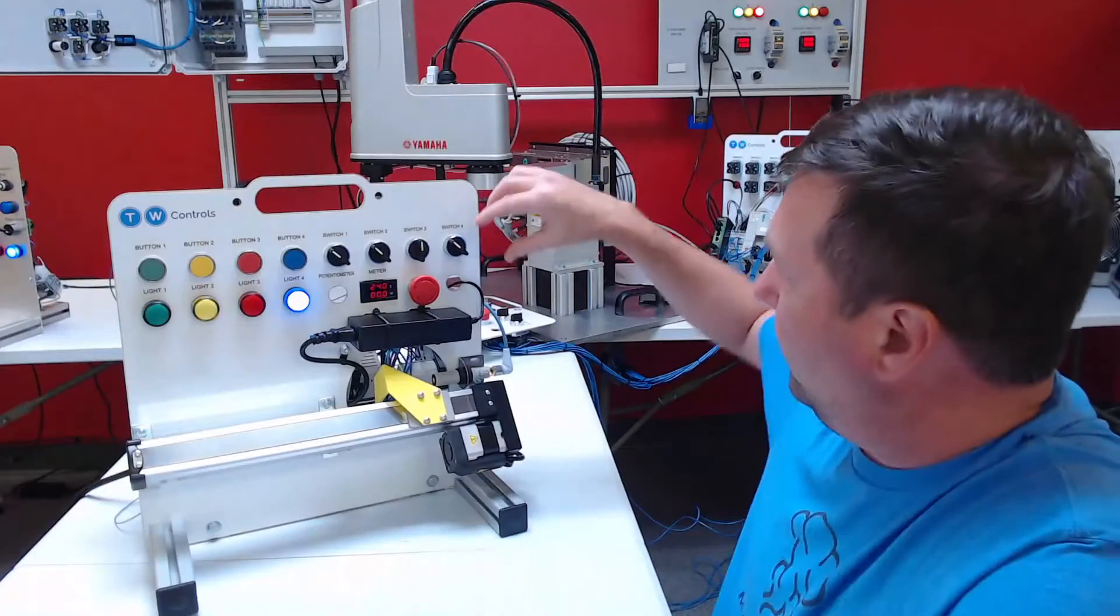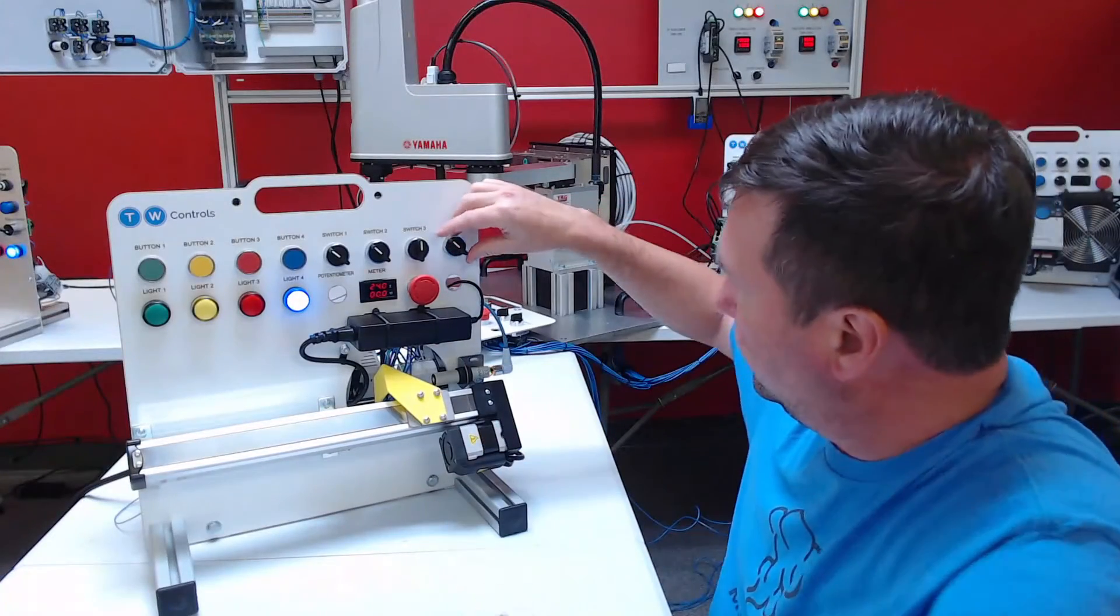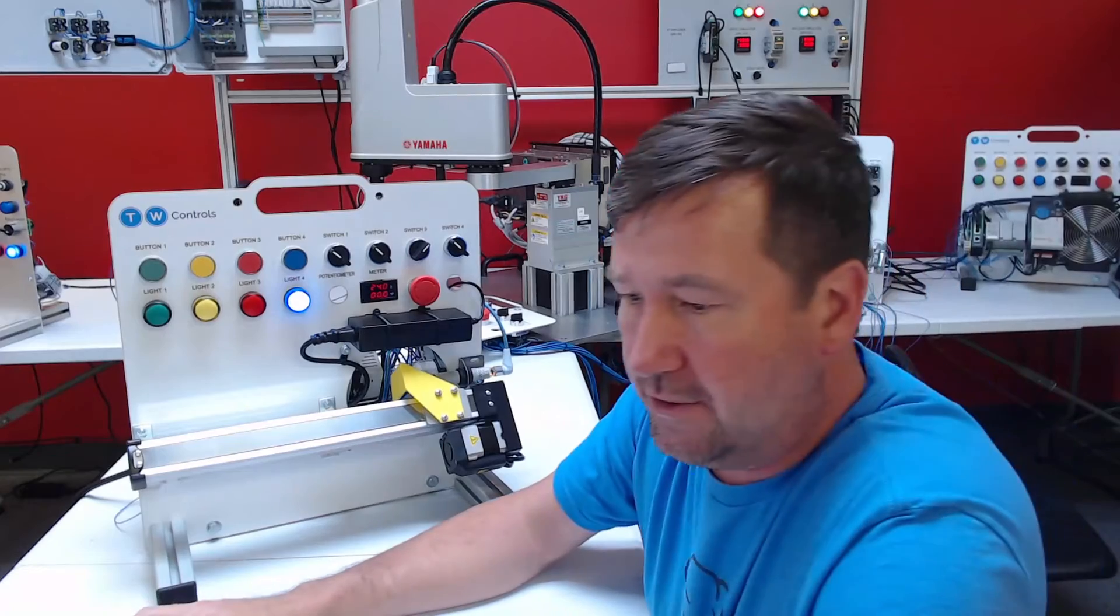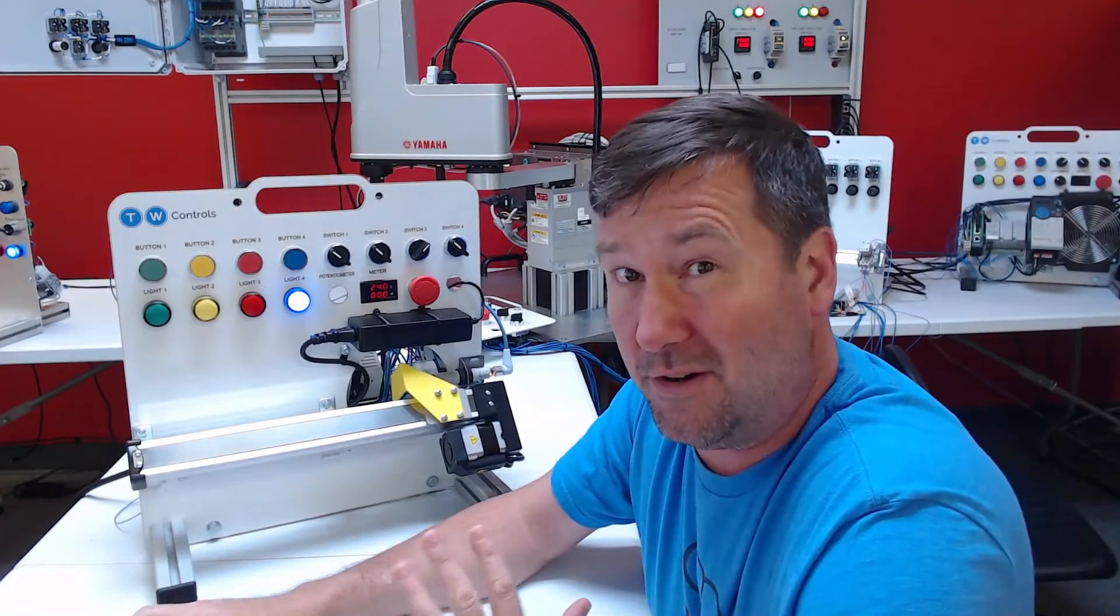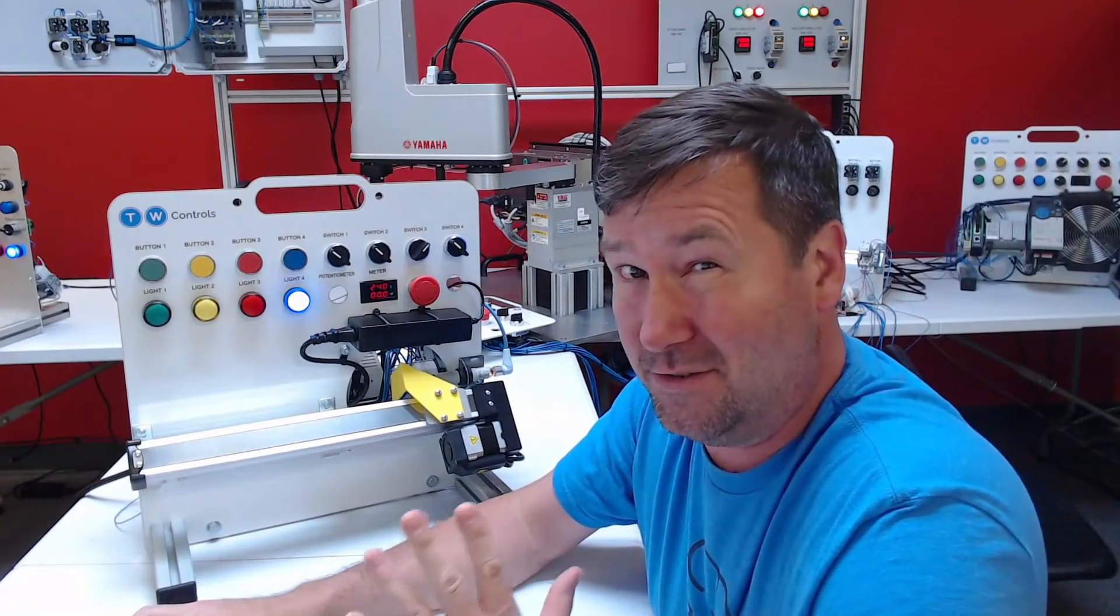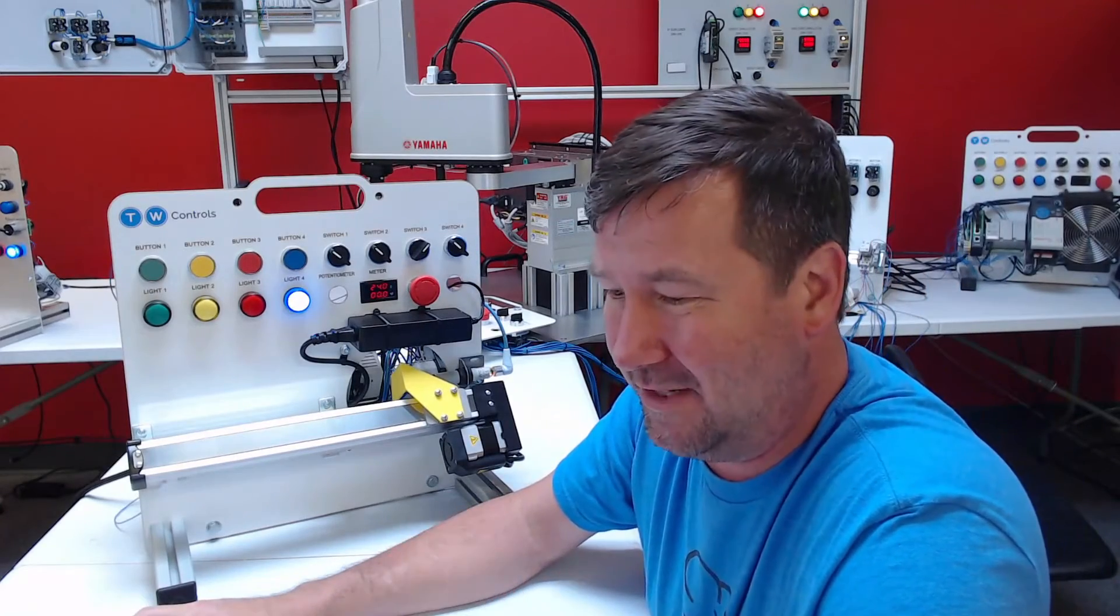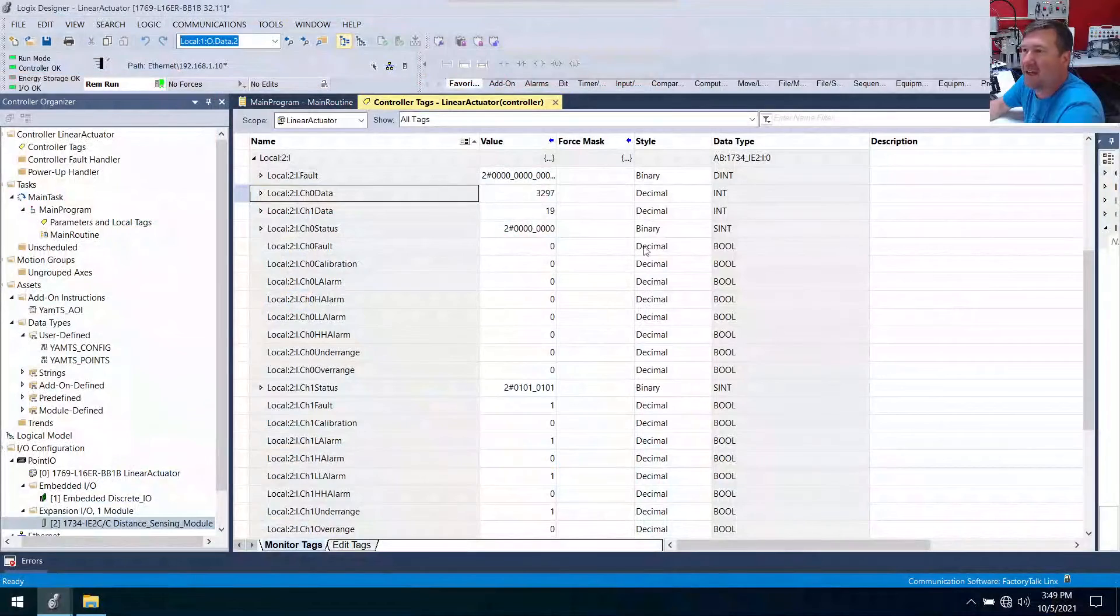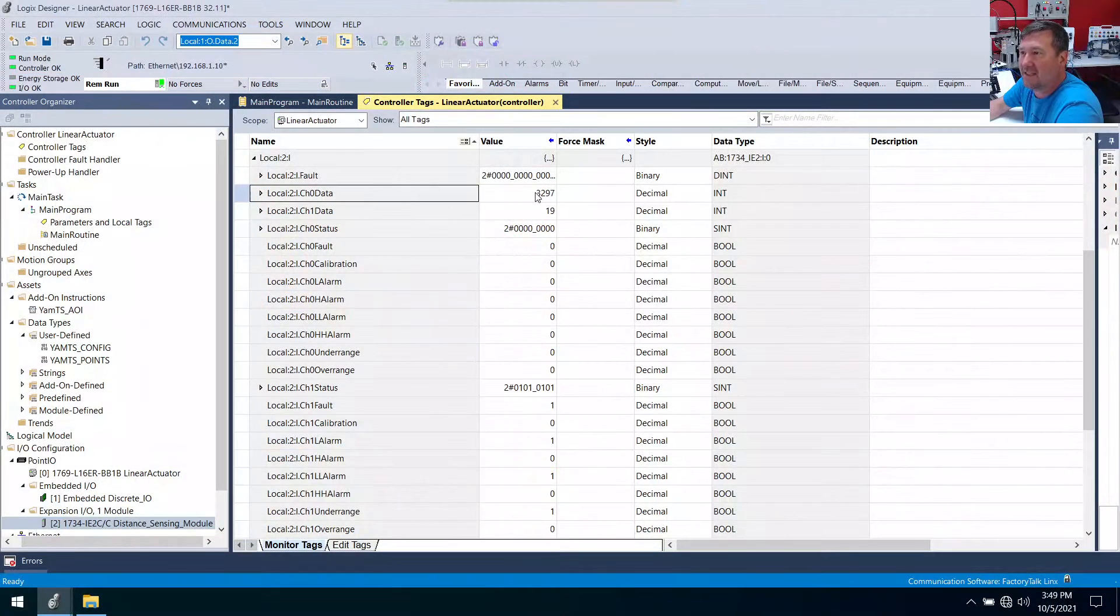First let's just make sure we see this. If I go very close to the right end then our value should be somewhere near 3277. It should be a little bit greater than that. And it is. It's at 3297. So we're slightly over 4 milliamp.